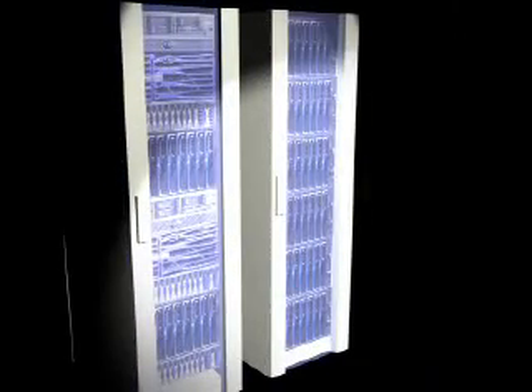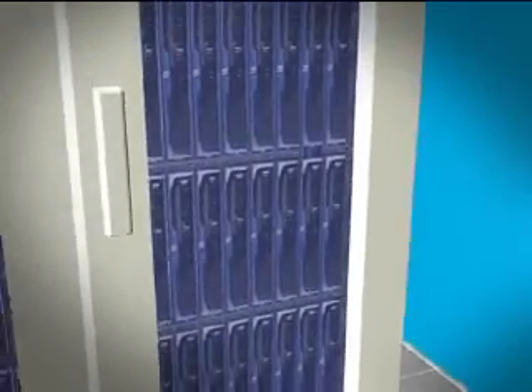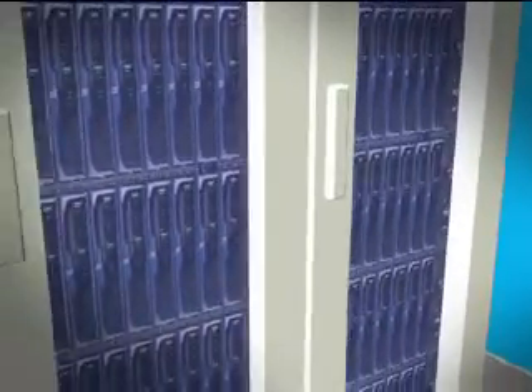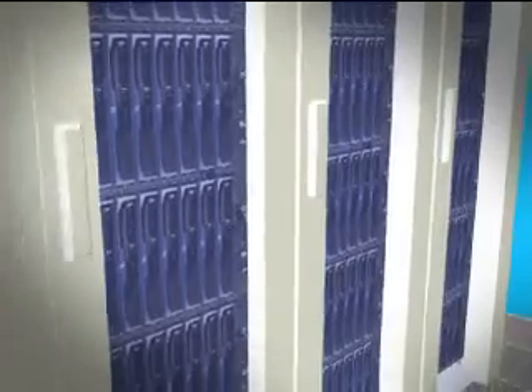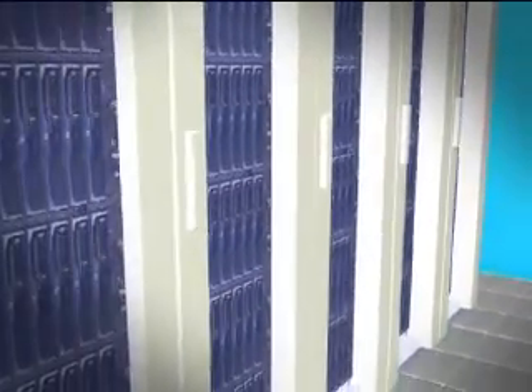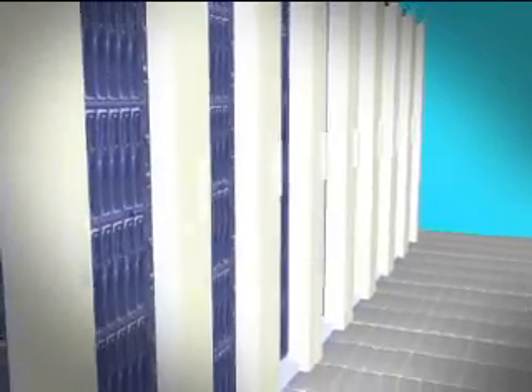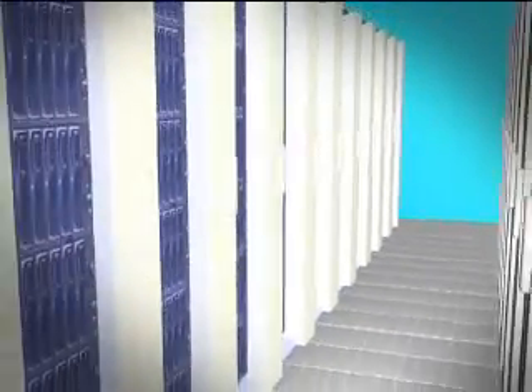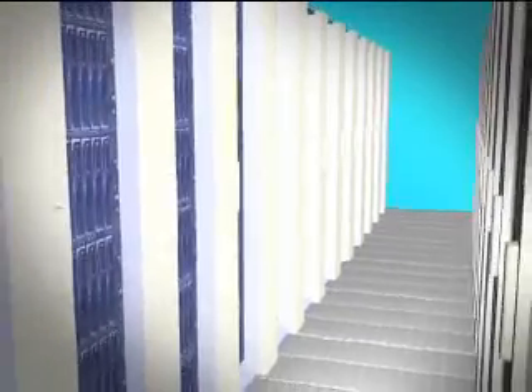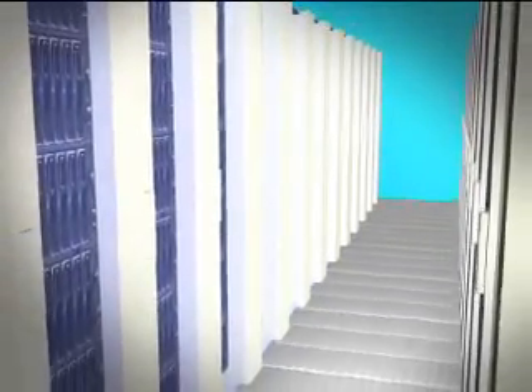A typical blade server can draw over 1.2 kilowatts within a 3U form. This means, in worst case, if you go top to bottom within an enclosure, you could be dealing with 20 to 30 kilowatts of heat. Not only do you need to handle the power, but very soon the implementation cost of installing a data center will be outweighed by the overall cost of running it.